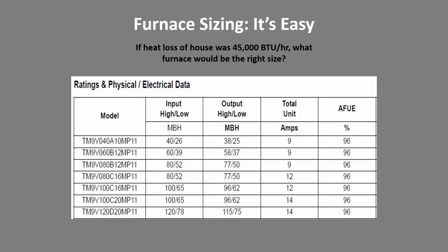You just sort of get the capacity tables out. This one here is for a two-stage piece of equipment. It tells you the input at 40K on high, 26K on low. The output, this is obviously a high efficiency furnace, is 38 and 25. And again, we size on the output of furnaces, not the input.